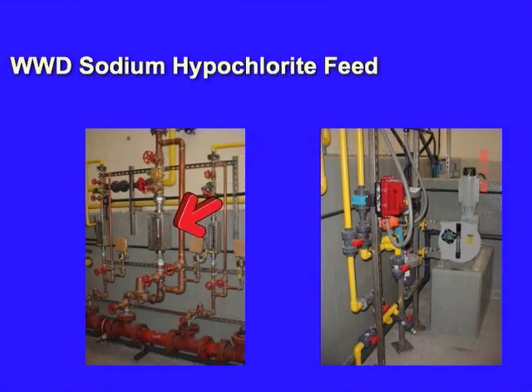You've got a bypass valve around this, and you want to make sure that that is shut. That's also in the O&M section; we put that in there. We changed it because at one point that was open and flowing around, and what it was doing was causing higher pressure to be sensed, and it was causing the pump not to start. Just enough pressure, with that not going through the rotor to have a head loss on it, okay? Why would the bypass be open?